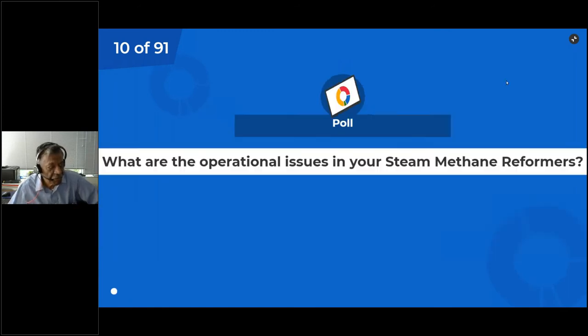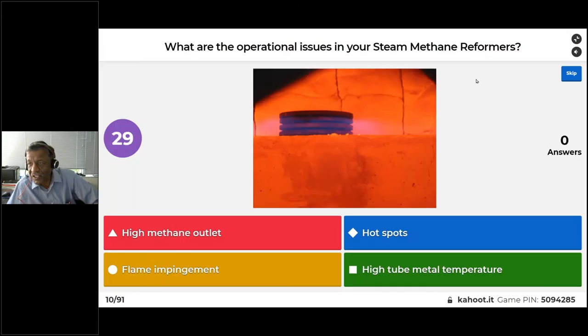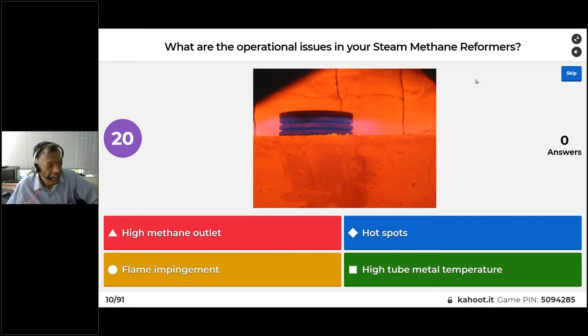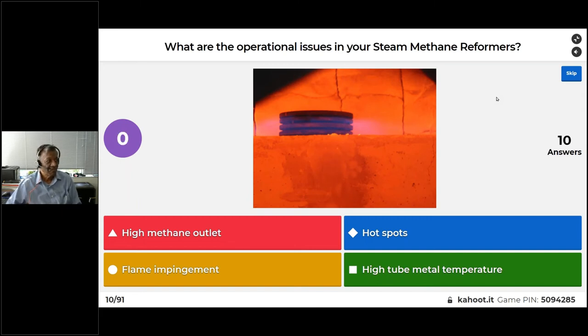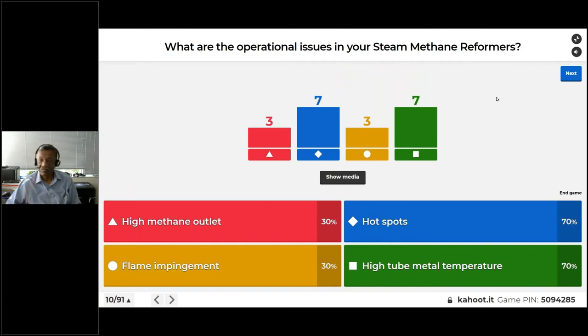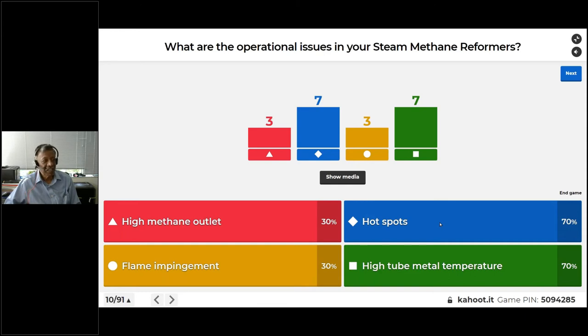I want to ask all of you: what are the operational issues in your steam methane reformers? Are you facing issues of methane slippage, hotspots, flame impingement, or high tube metal temperatures? We got quite a few responses — some have high methane slippage, some have hotspots. Hotspots and high tube metal temperatures are basically the same thing, plus flame impingement. Most of these issues are related to combustion, and we will cover all of that.